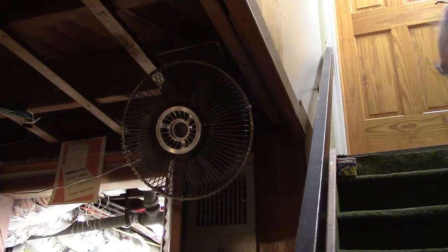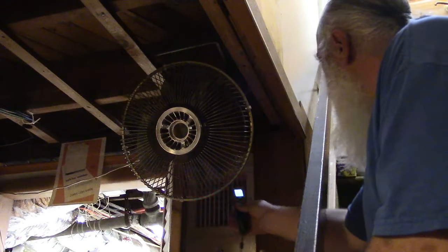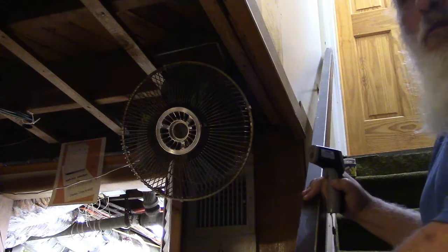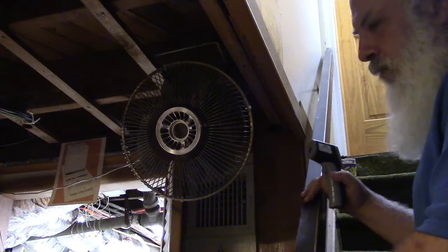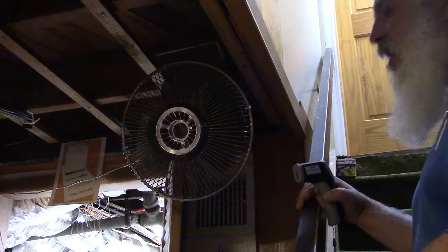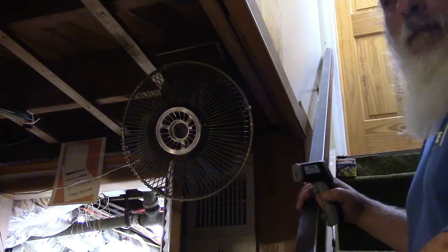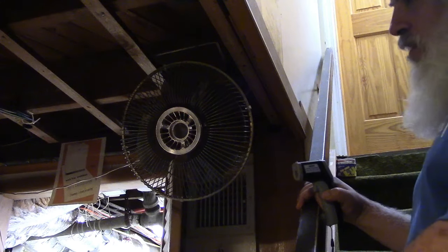Listen, I'm going to leave everything run for a while, start editing some other video, and I'll come back later. We'll test this again, we'll test the upstairs again. It's been about a good hour. 54, 53, 52 — that's pretty damn good. I can definitely live with that. I did shoot the vent in the kitchen before, which is one of the farthest runs, and that even has a booster fan on it, and that was reading about 55 an hour ago. So downstairs is working perfectly.